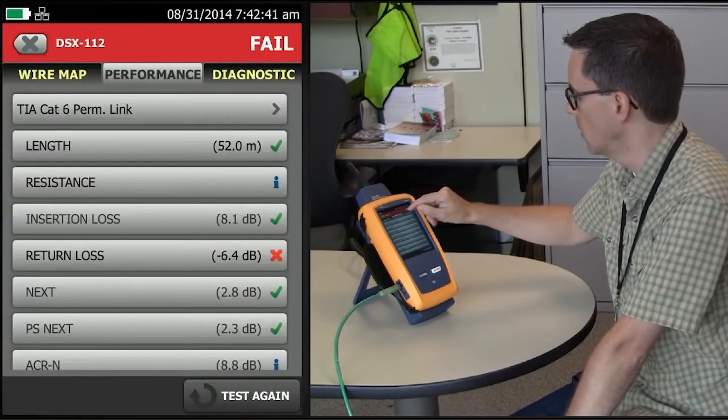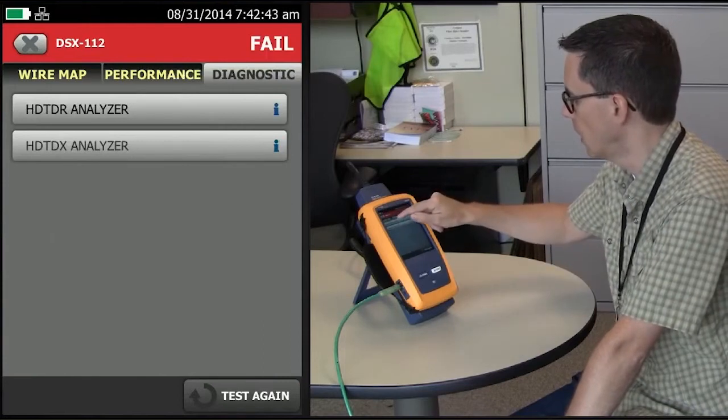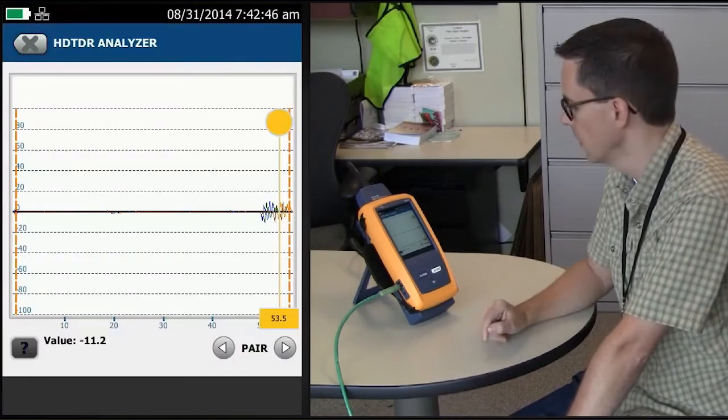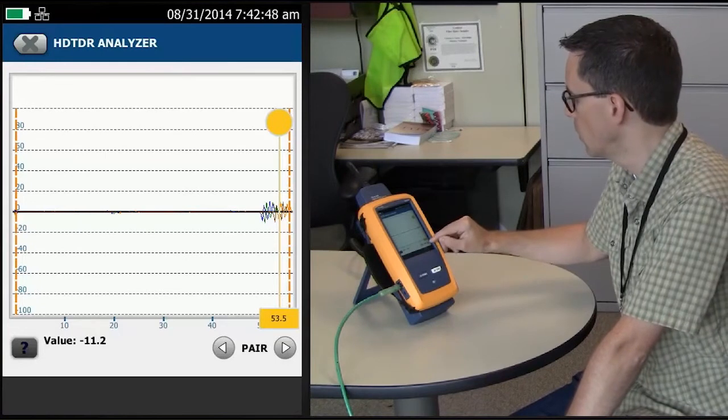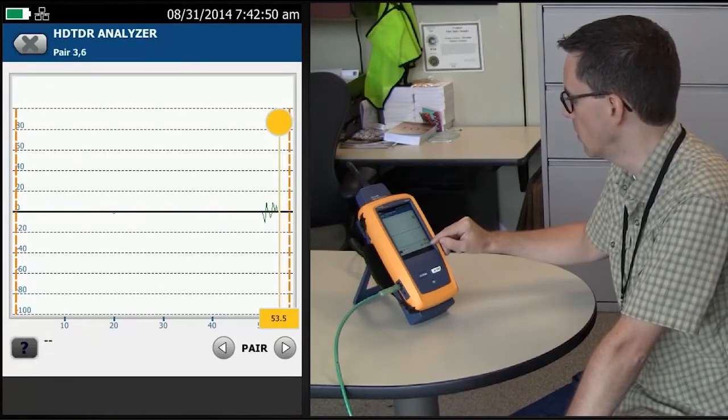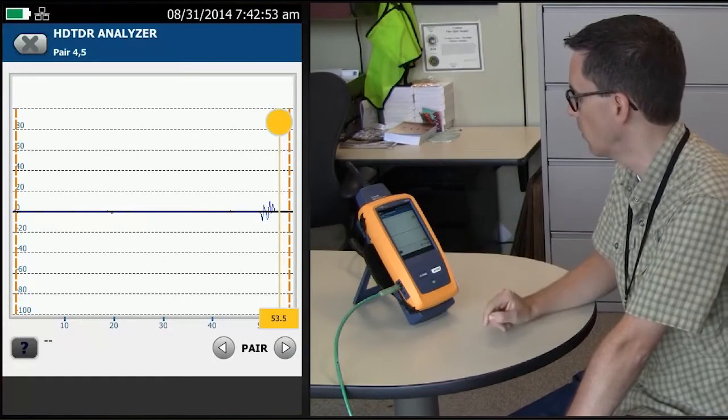We're going to go to our Diagnostic, our High Definition Time Domain Reflectometer. And I'm going to go to my shortest pair, because that's going to give me the most accurate distance to where the water is, which is 4-5.